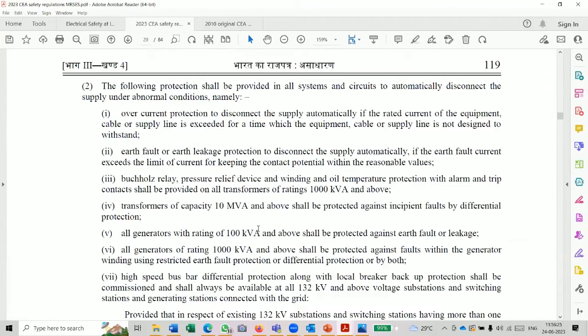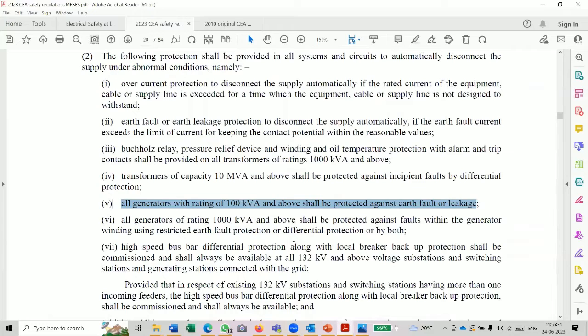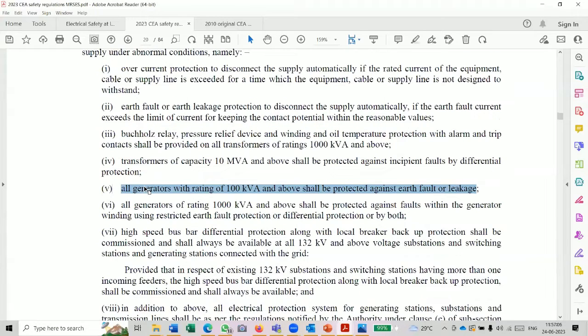Can we interpret these two things as applicable only if the voltage is exceeding 650? Exceeding 650 means 11 kV in our system, at least a minimum of 11 kV, no 650 existing now. So we should not interpret it as a voltage exceeding 650 because it is applicable for 100 kVA. There is no 100 kVA DG set at 11 kV. And an interlock is necessary for avoiding paralleling, for avoiding feedback. So we should interpret it out of common sense and science, and technically we should not strictly abide by the regulation. It has become a compulsion.